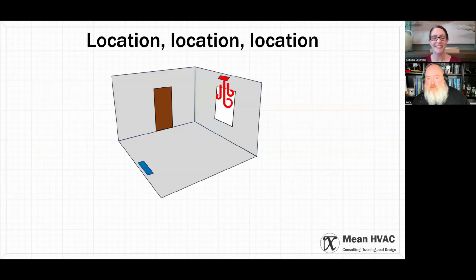Manual T has a lot of stuff in it about where to put things, the best way to do it, how to size it, and which flow pattern to use. It was written when that was a lot more important. It would tell you, say in Virginia or Massachusetts where I'm at, to put the supply on the outside wall and the return on the opposite wall for best airflow. If you were in Florida or Arizona, it would tell you something different—different climates call for different advice, and Manual T covers that.